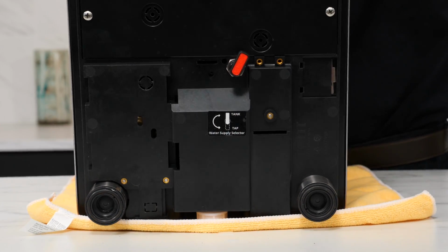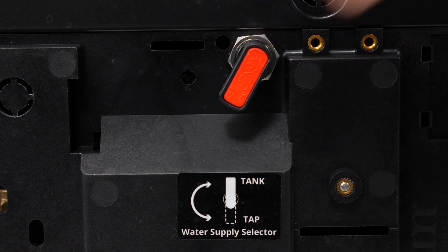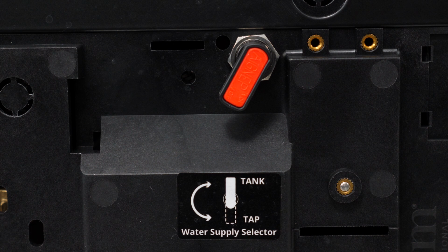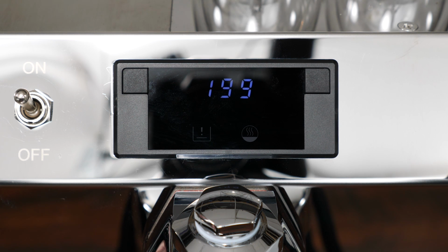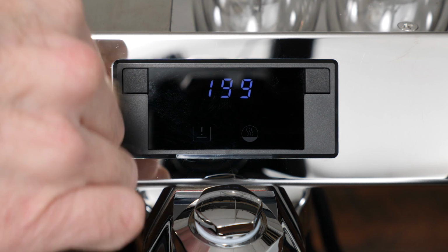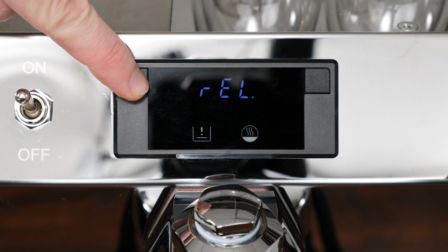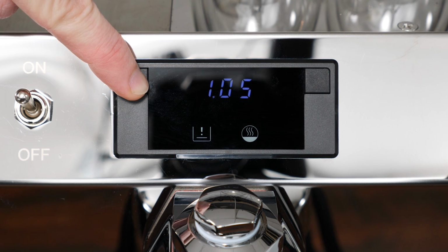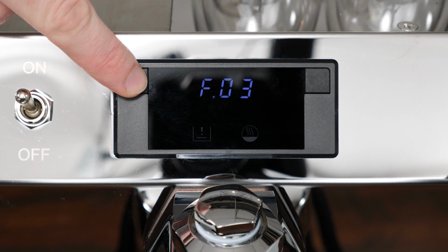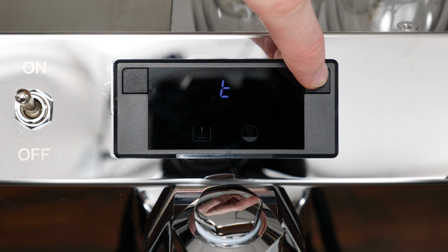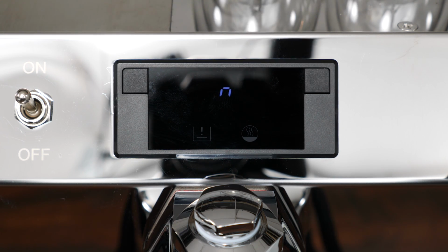If you are plumbing in the machine, you'll need to turn a lever on the bottom from tank to tap. You'll also need to go into the service menu and let the machine know you're using a direct line source. To do this, turn off the machine, then turn it back on while holding the left button. Scroll to A01 and change this setting to N for net.